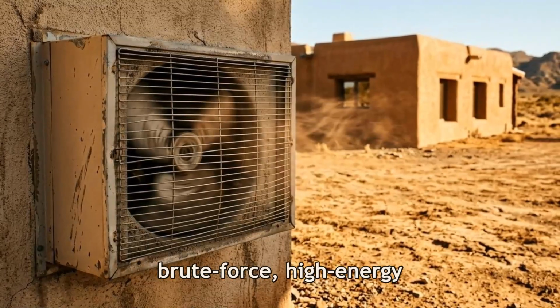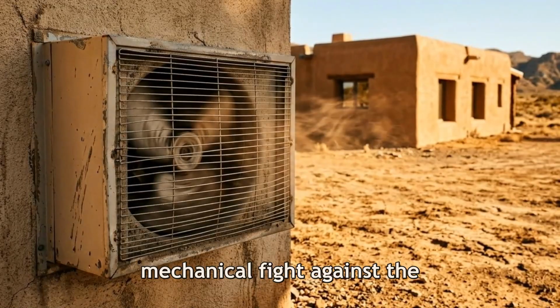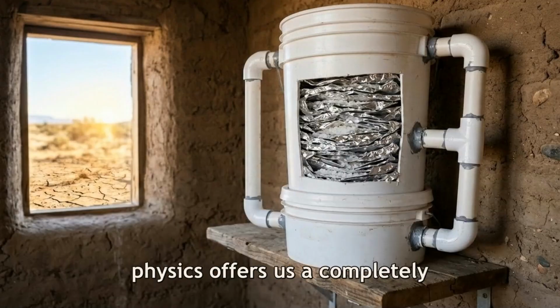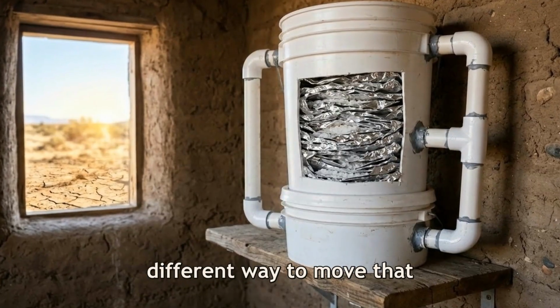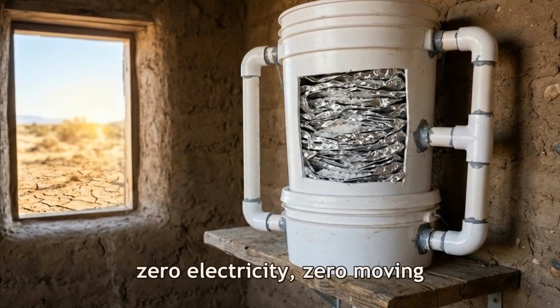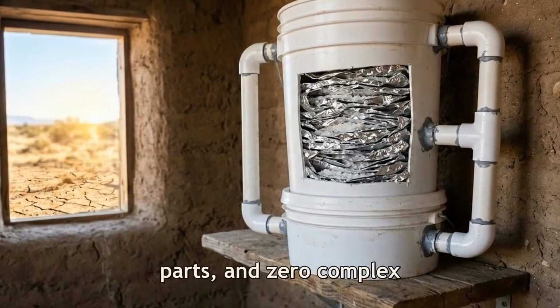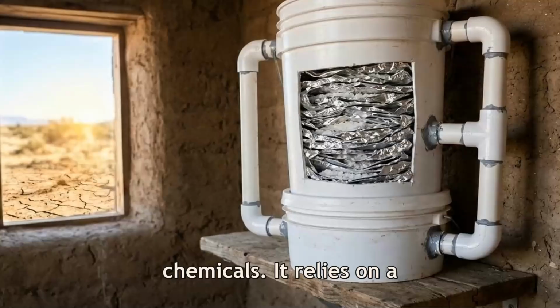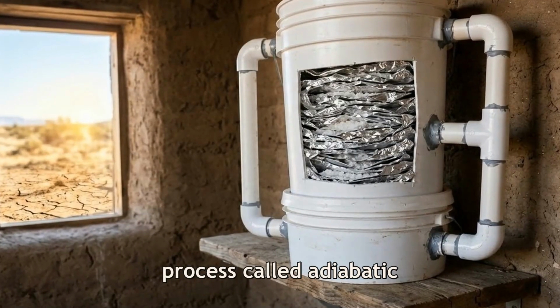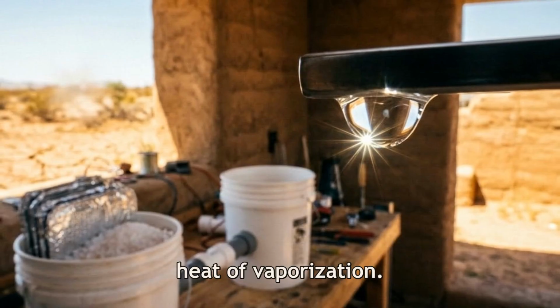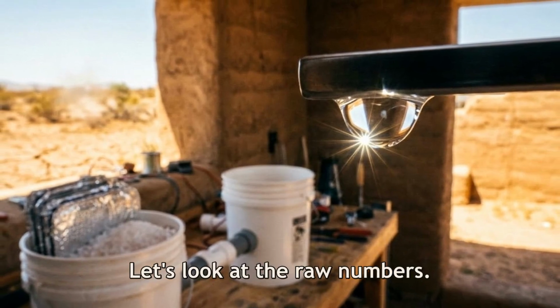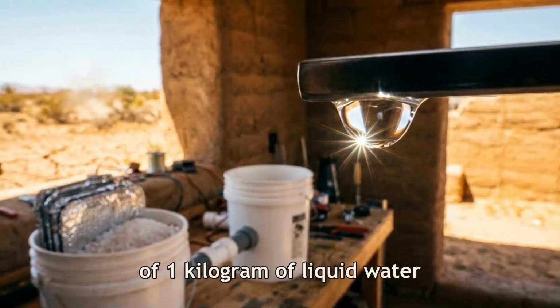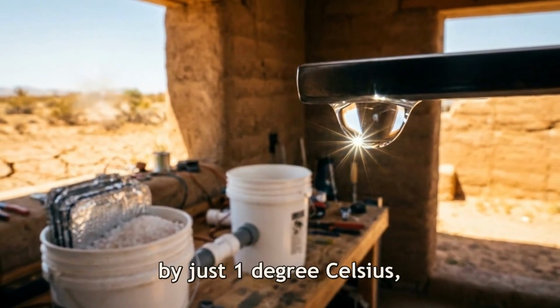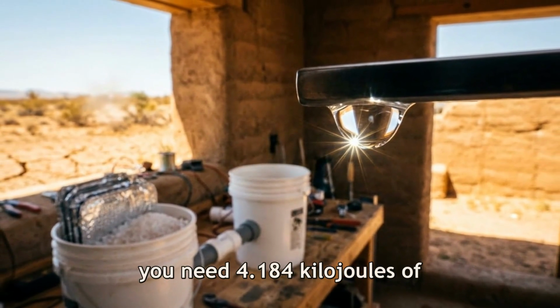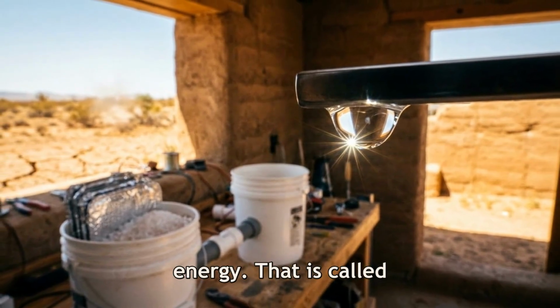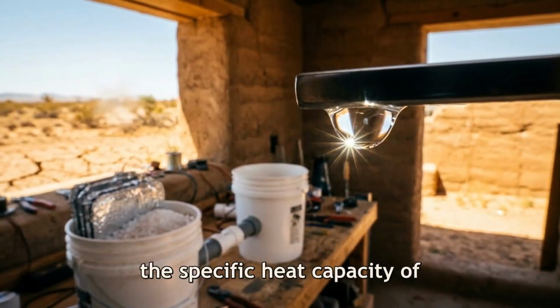It is a brute force, high-energy mechanical fight against the laws of thermodynamics, but physics offers us a completely different way to move that heat, a pathway that requires zero electricity, zero moving parts, and zero complex chemicals. It relies on a process called adiabatic cooling, powered by the latent heat of vaporization. Let's look at the raw numbers. To raise the temperature of 1 kilogram of liquid water by just 1 degree Celsius, you need 4.184 kilojoules of energy. That is called the specific heat capacity of water.